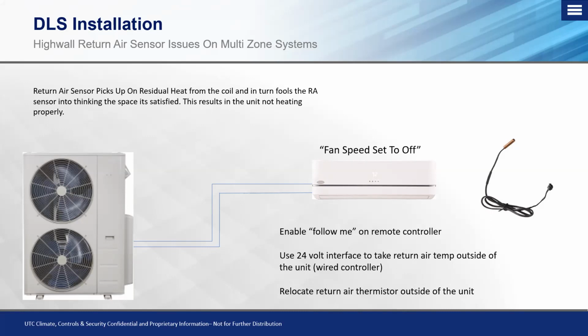Now, I call that a temporary solution because the follow me, I've seen periodically drop out of the follow me mode with inactivity on the remote controller. And then more commonly, when the system is enabled in follow me, it relies on line of sight communication with its indoor unit. So if you have a customer that you put in the follow me mode, it resolves their issue, the fan speed shuts off, and then you leave and run your next service call, and the customer puts it in a drawer or their kids take it and they get it lost. And it defaults back to the return air sensor if it's not within line of sight to that indoor unit, and then the problem returns, which is why we call that a temporary solution, while relocating the return air thermistor is more of a permanent fix.